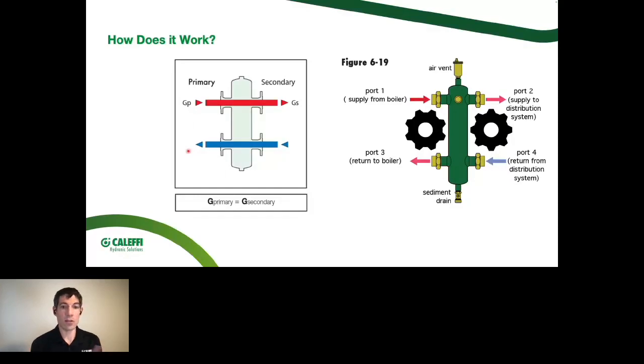So in a one zone snowmelt system, that could be a good way to go. You could save a little bit of money there as long as your circulator can overcome the pressure drop of both the PEX pipe going out into the snowmelt and the boiler heat exchanger and all of the distribution piping in between. If your boiler circulator can take care of both of those, maybe you don't need a system circulator. So kind of a rare example, I would argue. Most systems are going to have multiple zones, and that might put you into a situation where one circulator to take care of both sides could be a commercial circulator that would be more expensive than buying two more residential size circulators that just take care of each side of the equation independently. So even in a single zone snowmelt system, a primary-secondary device wouldn't hurt anything, but it may be something that isn't required.